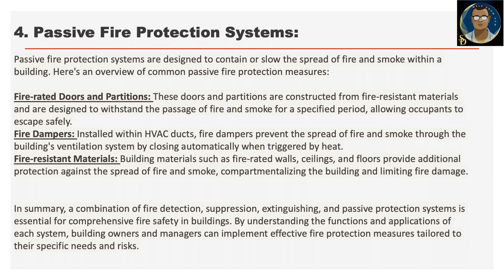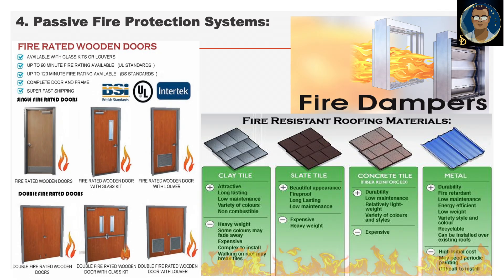Passive fire protection systems are designed to contain or slow the spread of fire and smoke within a building. Common passive fire measures include: fire-rated doors and partitions, which are constructed from fire-resistant material and designed to withstand the passage of fire and smoke for a specified period, allowing occupants to escape safely. Fire dampers installed within HVAC ducts prevent the spread of fire and smoke through the building ventilation system by closing automatically when triggered by heat. Fire-resistant materials such as fire-rated walls, ceilings and floors provide additional protection against the spread of fire and smoke.